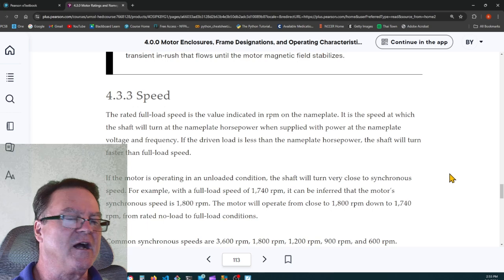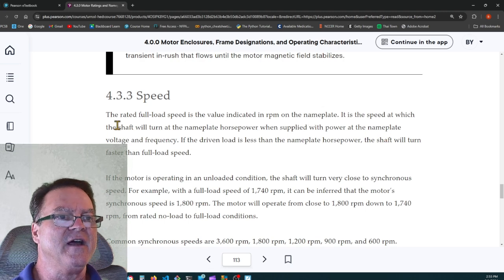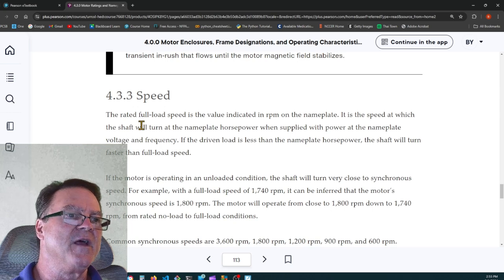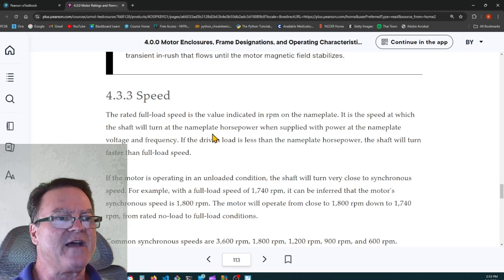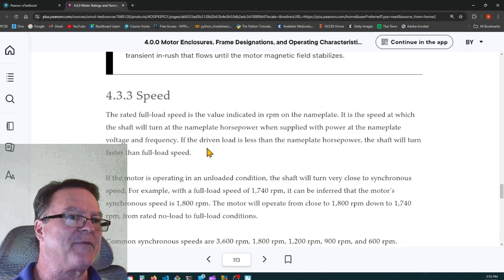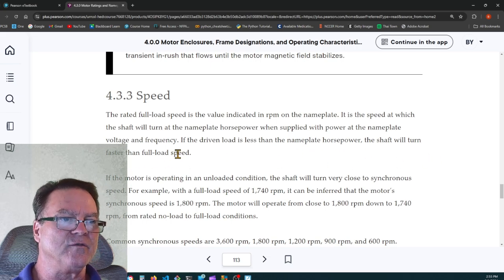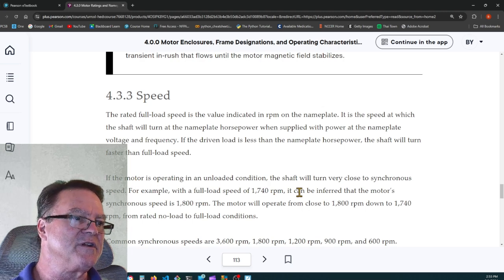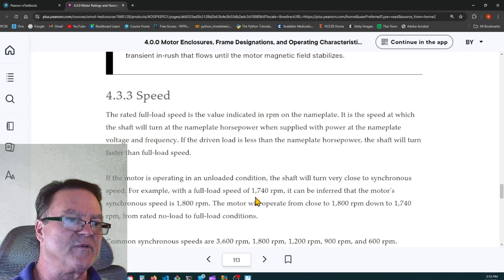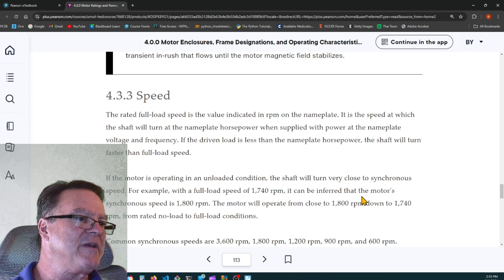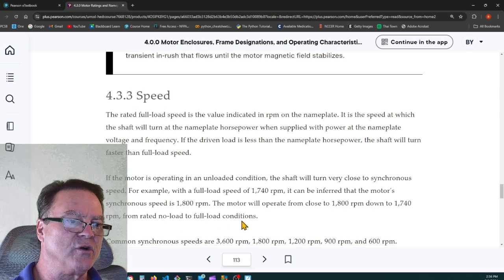It's only for a split second. A couple of half a second, 1 second, 2 seconds, that thing is rotating and it's creating CEMF, and it should be up to speed within 3 seconds. The rated full load speed is the value indicated in RPMs on the nameplate. It's the speed at which the shaft will turn at the nameplate horsepower when supplied with power at the nameplate voltage and frequency. If the driven load is less than the nameplate horsepower, the shaft will turn faster than the full load speed. If the motor is operating in an unloaded condition, the shaft will turn very close to synchronous speed. For example, with a full load speed of 1,740 RPM, it can be inferred that the motor's synchronous speed is 1,800 RPM. The motor will operate from close to 1,800 RPM down to 1,740 RPM with rated no load to full load condition.